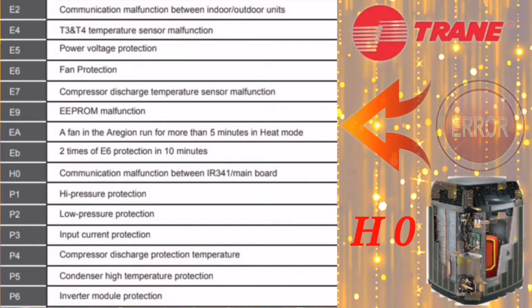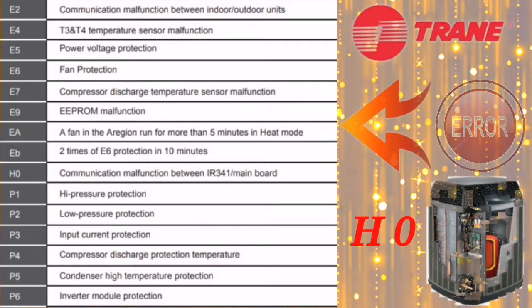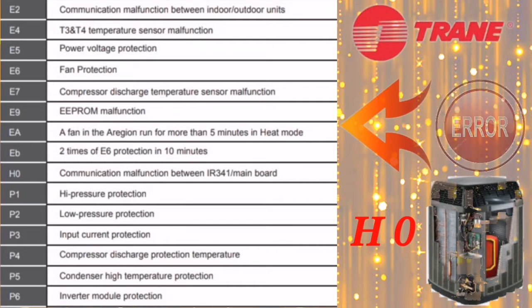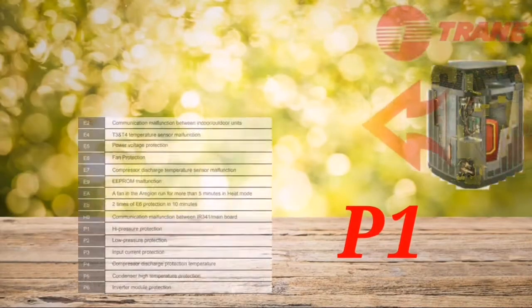The next error code is H0, which means communication malfunctioning between the IR module and the mainboard. When you get error H0, either the mainboard, the outdoor PCB, or the indoor PCB is faulty. To diagnose, check the output supply of the communication cable from the indoor PCB — it should be between 13 to 24 DC volts. If you don't get that voltage from either the indoor or outdoor unit, the respective PCB is faulty and needs to be replaced.